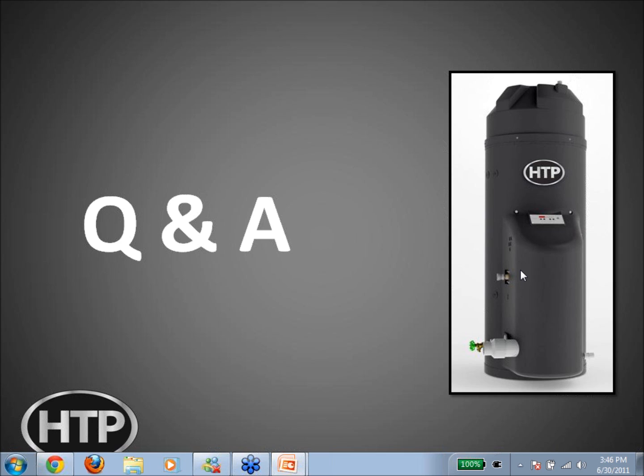Any plans for ASME? At this point, no, because of some of the restrictions and the costs related to building a tank of that volume in an ASME construction. We don't feel it would be competitive. Is unequal venting acceptable? Can combustion air be taken from inside the space? And is flexible venting usable? Yes, most definitely. You can draw room air from the space.